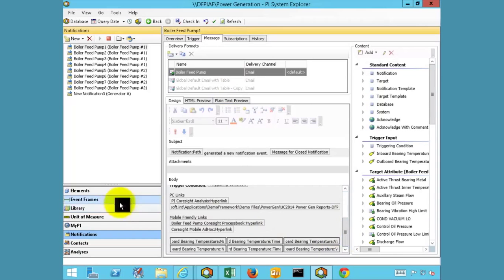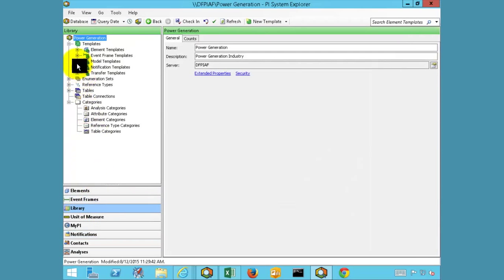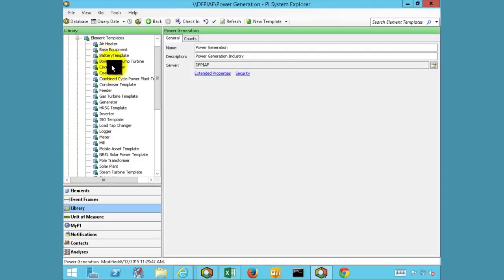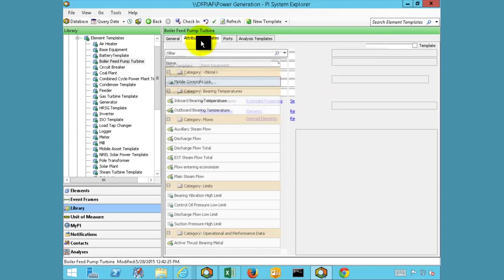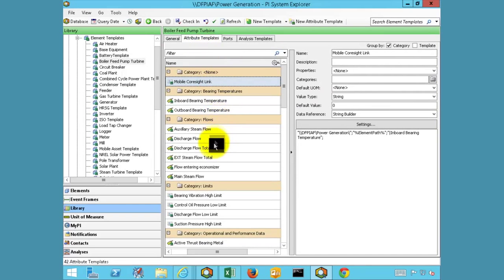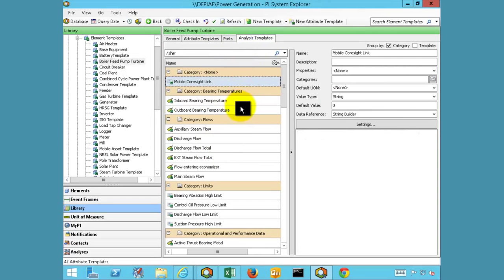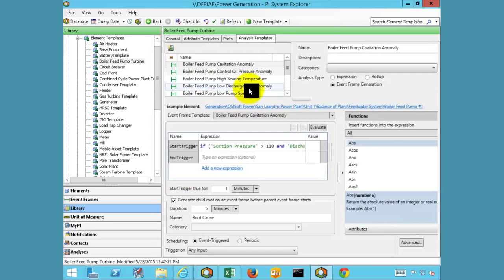As was stated previously, all of the configuration for our boiler feed pump is stored within the boiler feed pump template. Making changes to this template will result in making changes to all the unique instances of the boiler feed pumps that have been governed by this template. As such, if we need to add some new data to the template, or we need to add a new analysis to create additional events, adding them to the template will roll them out rapidly to all of the unique instances within our database. This greatly simplifies not only the initial creation of assets within the AF database, but also reduces the time spent on future administrative efforts.